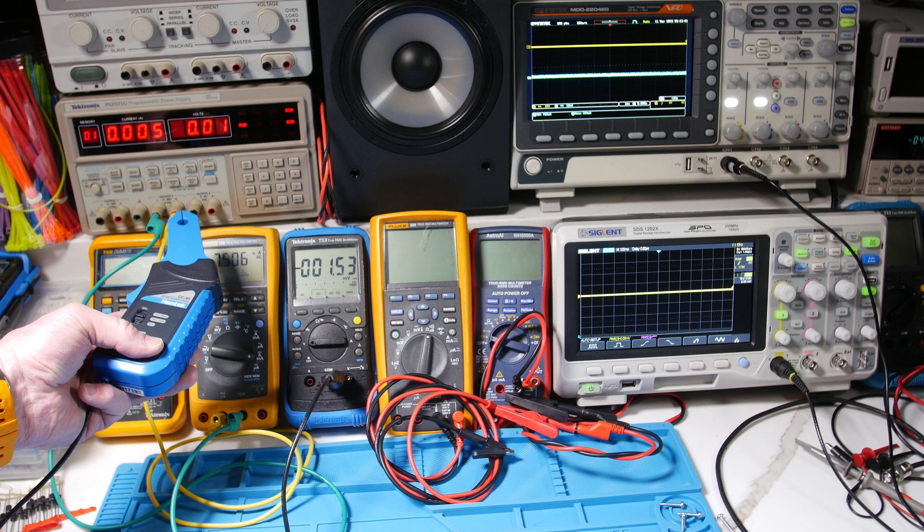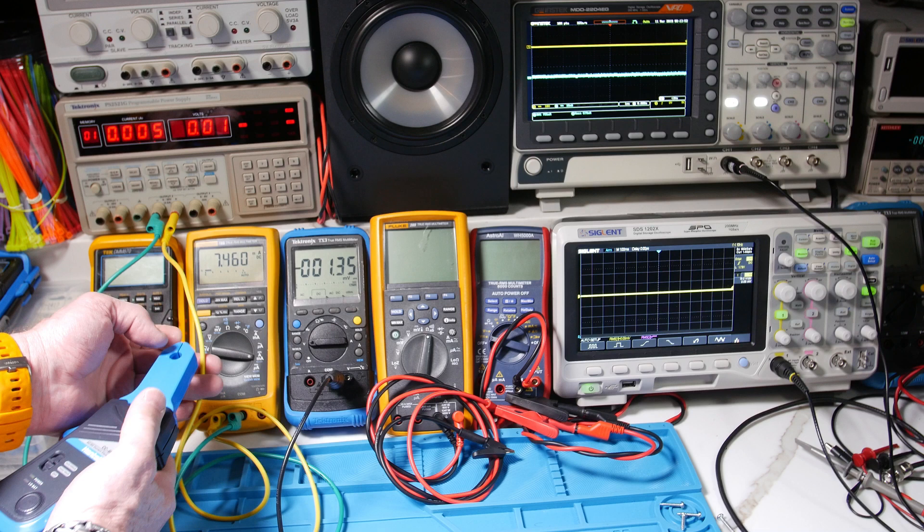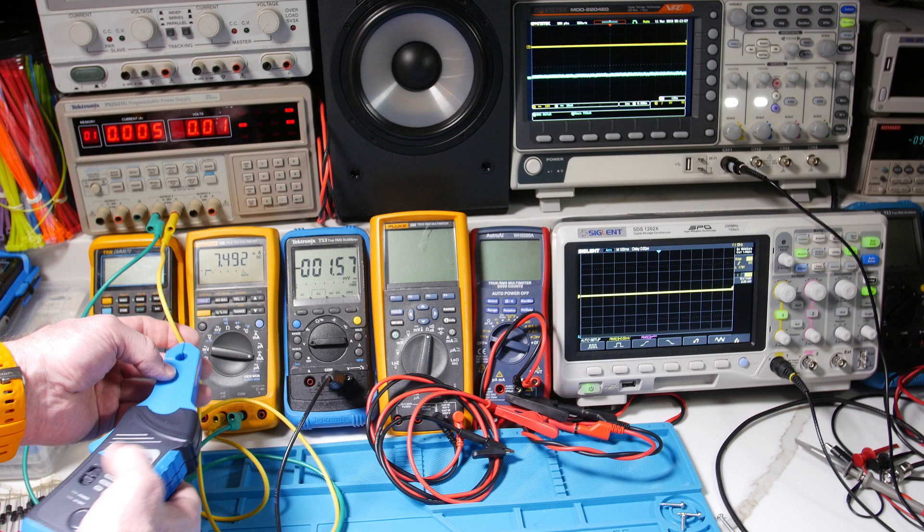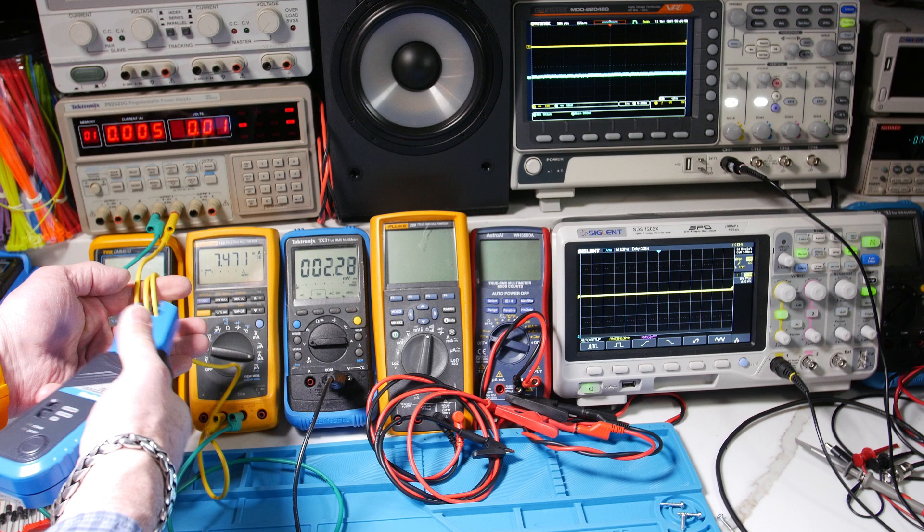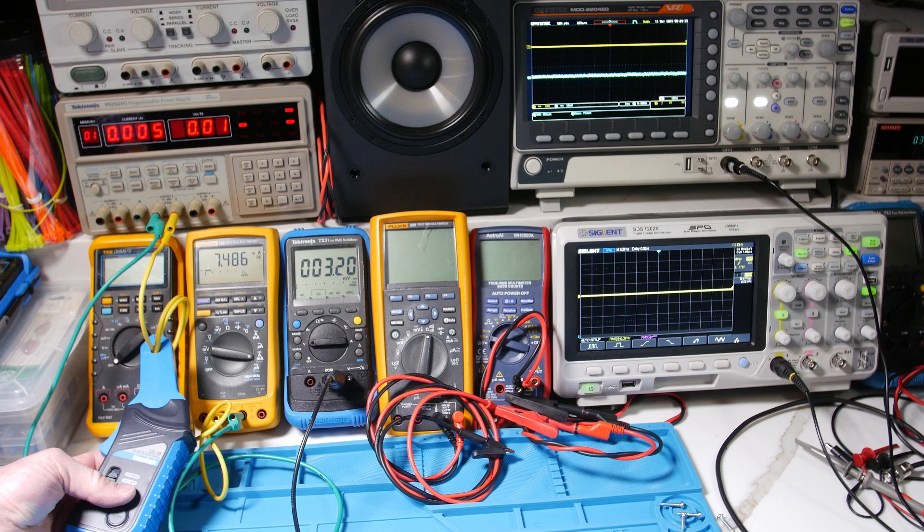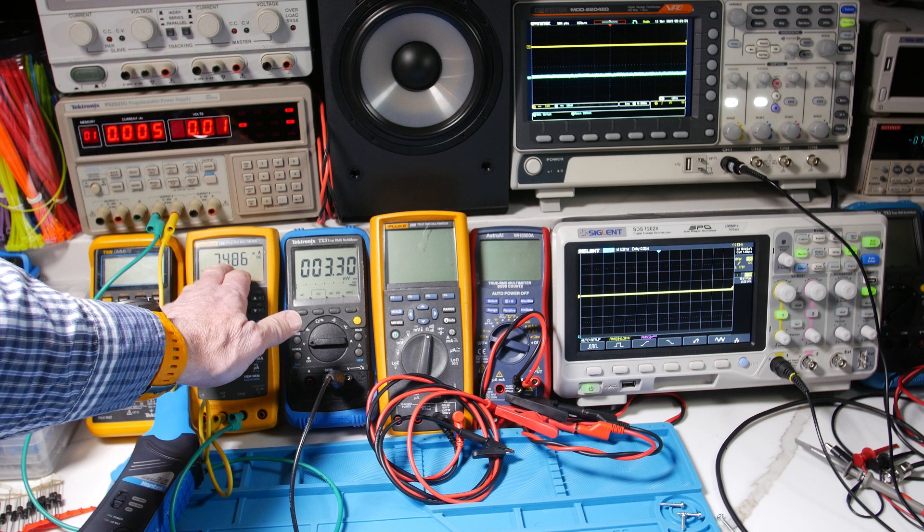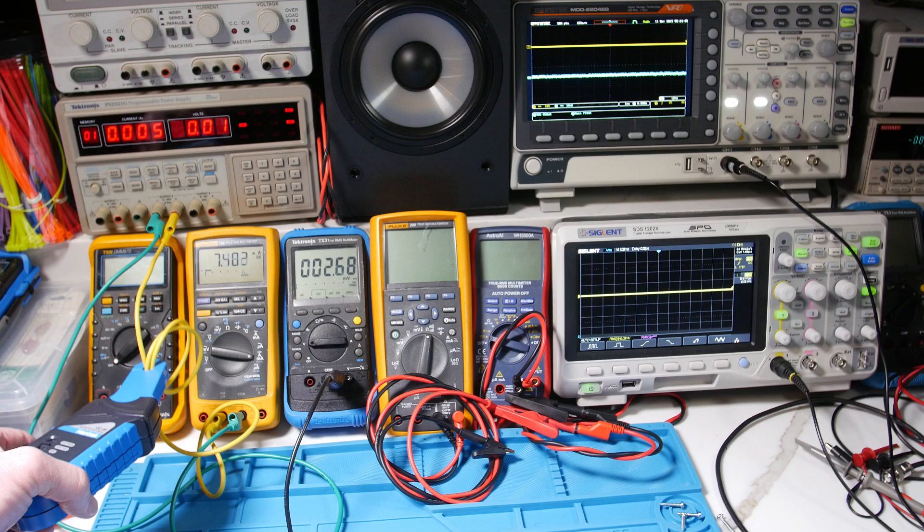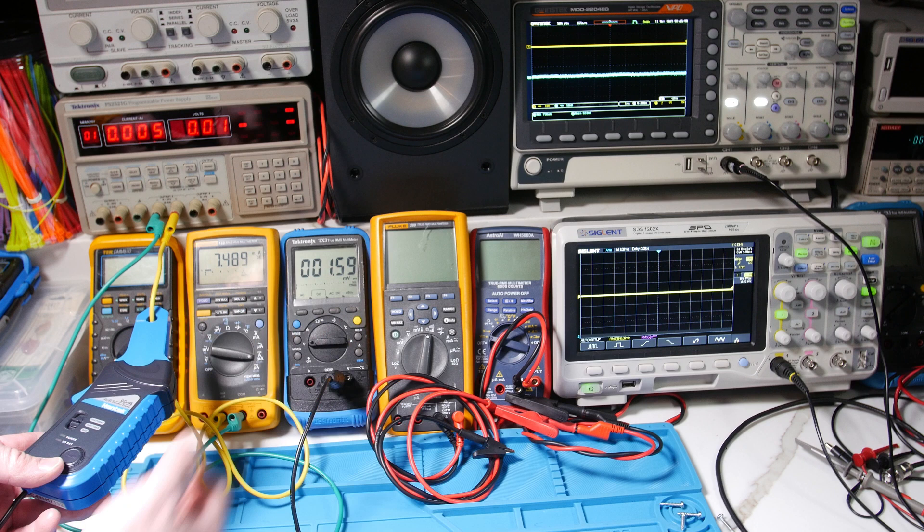Okay, now what if you did this? The current goes through this thing and creates a magnetic field, okay? So it's like a transformer. I don't know how many turns are in here, but this is like one turn. What if instead of doing one turn, here I'm going to degauss a couple times. What if instead of making one turn, what if we do two, let's say three, let's say four turns. Let's try three. I don't know if I can get four in there. Okay, that's three turns. So you multiply that by 10, that's 32. Divide by three, that's about 10. So it's a little bit closer to 7.5. So we are getting a little bit, we are getting some better accuracy. At least, we're able to get something close to this, where if we only do one, it's way off. That's like 16 milliamps.